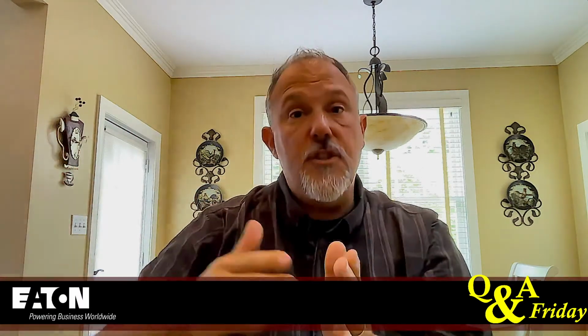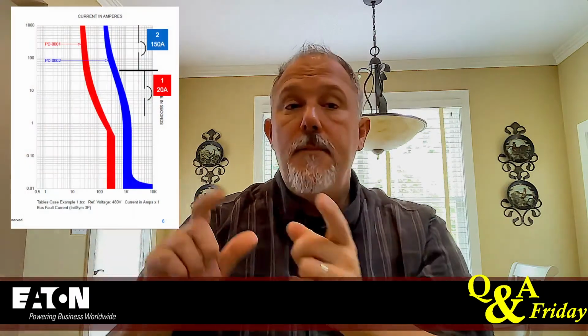And you may say, I just used the tables, go away, leave me alone. If you do that, you definitely will have a problem because you have to adjust your long time pickups, your short time pickups, your short time delays, your long time delays. All of that has to look good on the curve. They have to have separation all the way down, except for when the fault current is greater than the instantaneous on both sides, like these two curves.